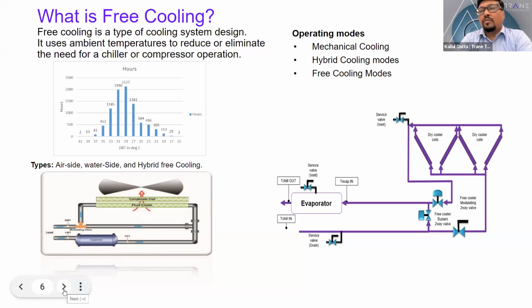Let's understand from this circuit. Return water coming from the load, that is from the server, if the ambient temperature is more than 37 degrees centigrade, will go directly to the evaporator. It will never enter the free cooling circuits. So the mechanical cooling circuit will be activated and the compressor will be fully throttled to make sure that the desired chilled water set temperature is met.